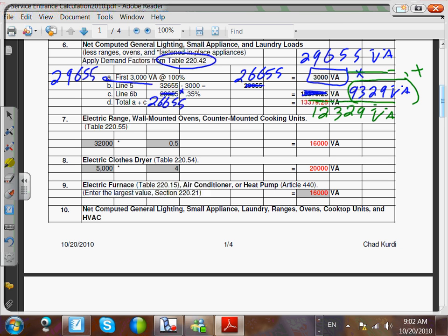That's my calculated value. So what did I do, guys? I took all the stuff that I did so far and derated them. That's all I did. I want you to highlight this number in a different color, because that's the number we're going to carry all the way down through the sheet. Why? Because it's already derated.